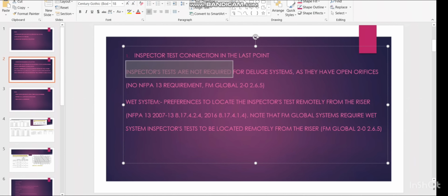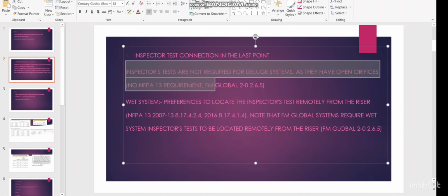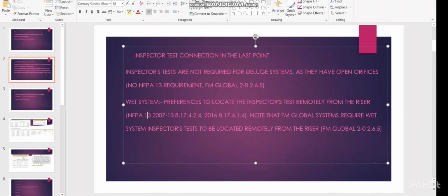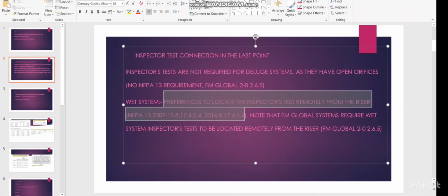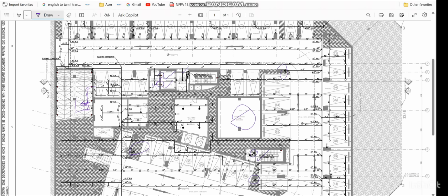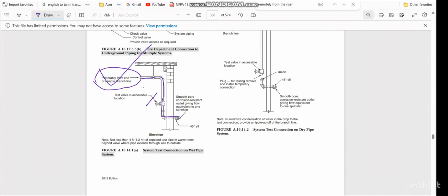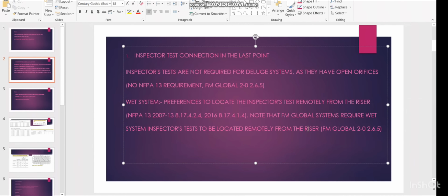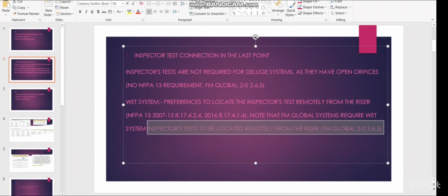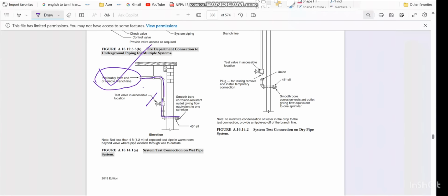Inspector tests are not required for a deluge system as they have open orifices. There is no NFPA 13 requirement; this is for the Factory Mutual Global requirement. Coming to the wet system, the preference is to locate the inspector test remotely from the riser. In NFPA 13 2007 you can see this reference. In NFPA 13 2016 you can see this reference, and this is what I showed in the recent edition also. They have mentioned this point. And coming to Factory Mutual Global, they also have the same rule. Note that Factory Mutual Global systems require the wet system inspector test to be located remotely from the riser. They have given the reference also. So all these standards recommend that this should be far away from the riser.